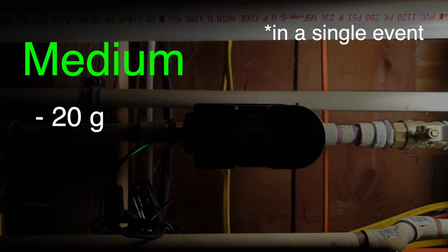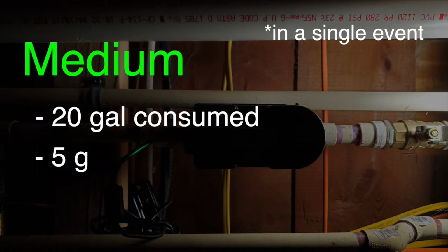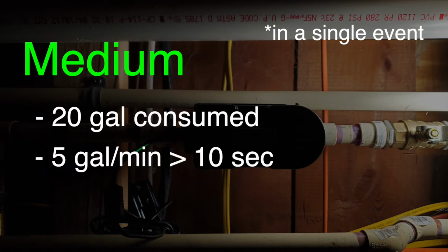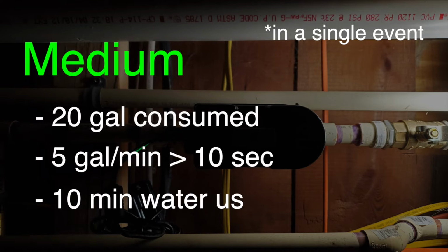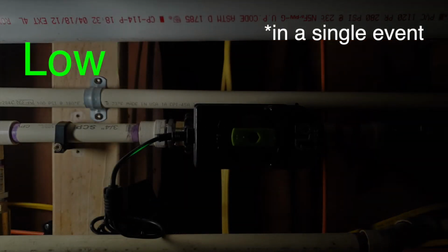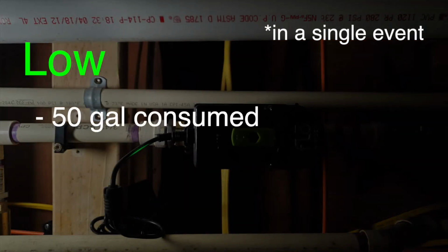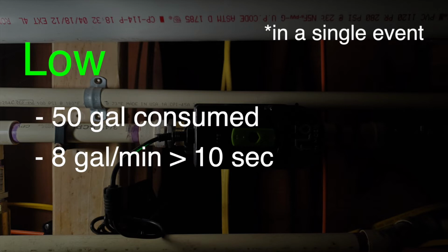Medium triggers shutoff at 20 gallons consumed, 5 gallons per minute for more than 10 seconds, or 10 minutes of water use. Low allows for 50 gallons consumed, 8 gallons per minute for more than 10 seconds, or 15 minutes of water use. The gotcha for builders here is making all trades aware of this device protecting the home.